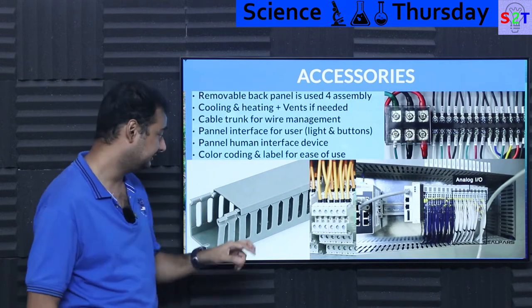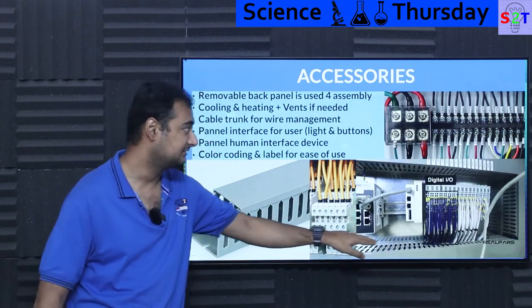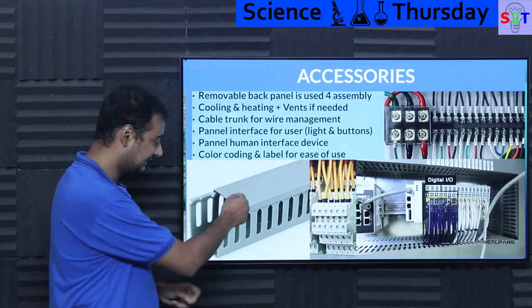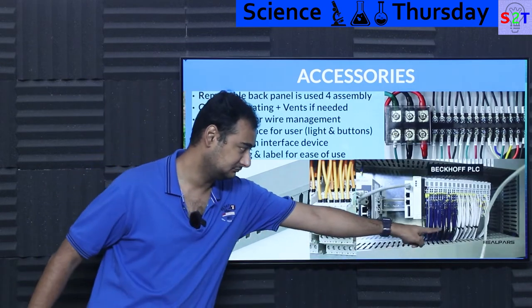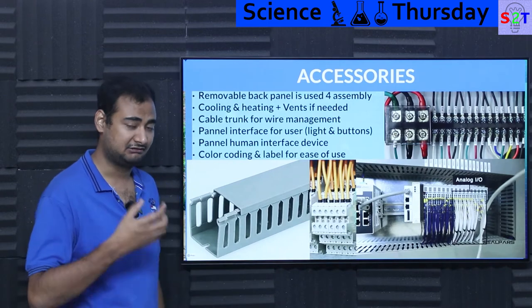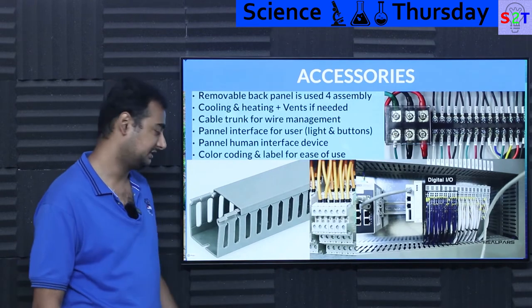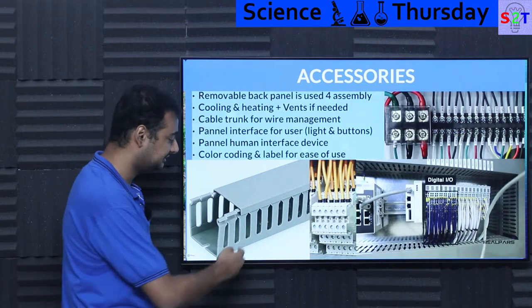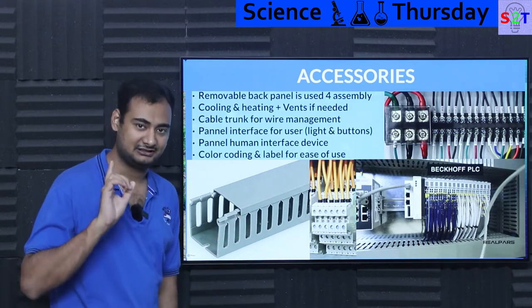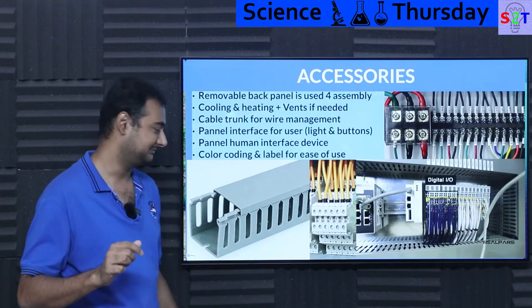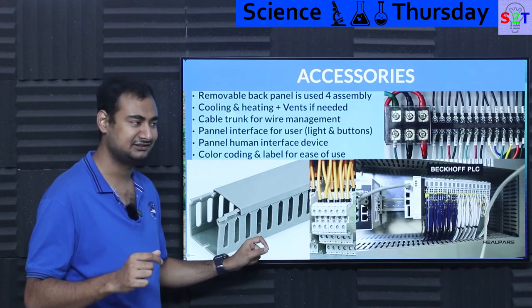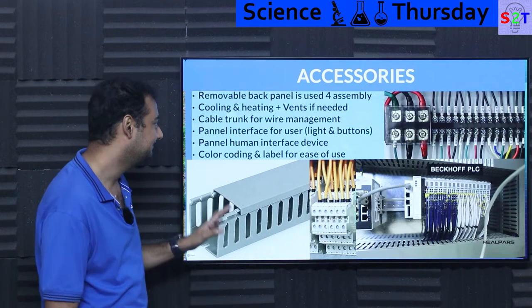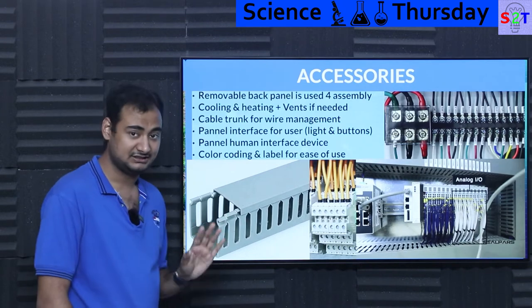Cable trunks are the primary thing you will always see in these gray-style boxes — specifically designed with slot holes so small wires pass through easily. If you have giant thick three-phase wires, you can break off the fingers on the trunk to create larger openings. Be mindful though: those fingers are one-way — once broken off, there will be a gap there permanently. Cable trunks are for wire management.